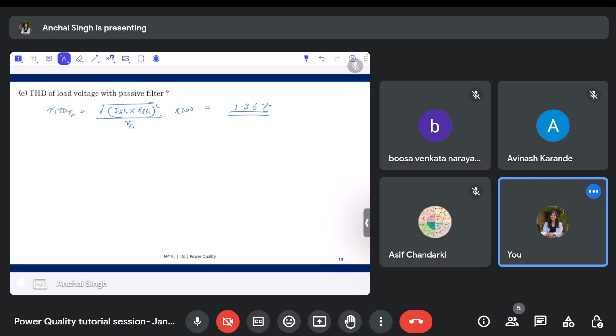In the next part, we have to calculate the VA rating of the passive filter. We know the voltage rating, we just have to calculate the current rating of the passive filter, which is again given by the square root of IS square minus IS1A square minus ISH square. It will come out to be 162.815 amperes. And therefore the VA rating of the passive power filter is VPF into IPF. Since it's three phase, it will be 3 times Vs into IPF, which is 3 times 415 by root 3 into 162.815, which will come out to be 117.031 kVA.